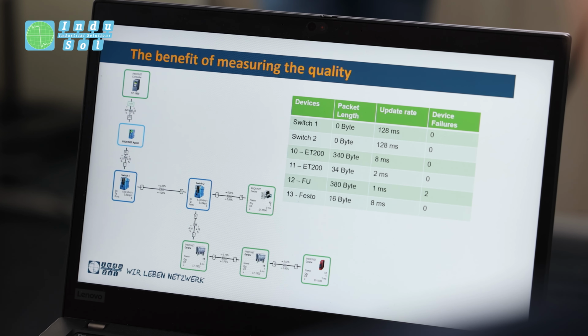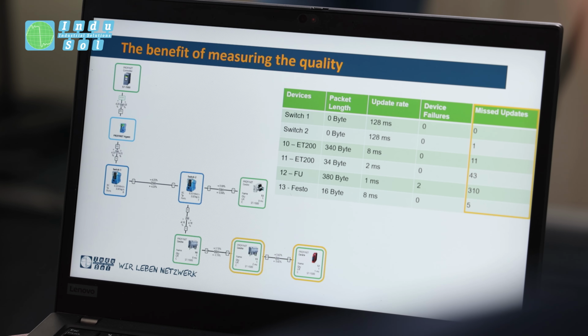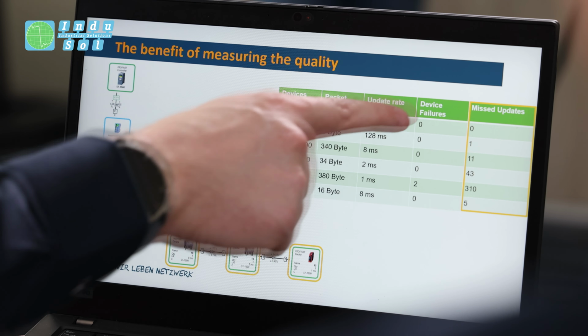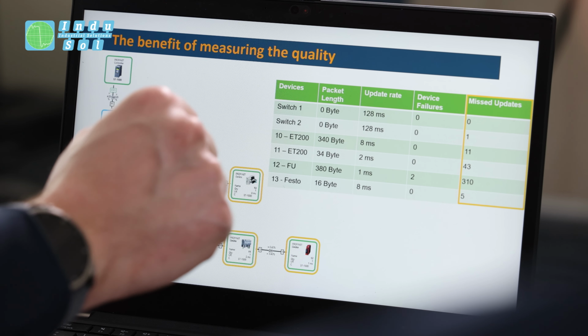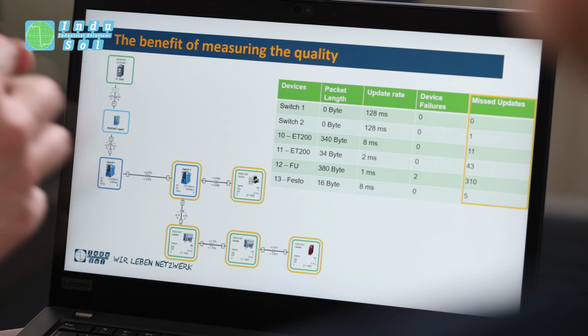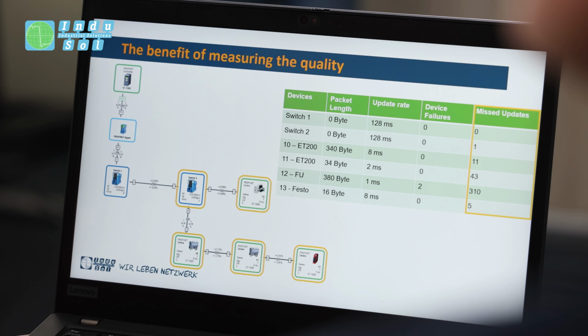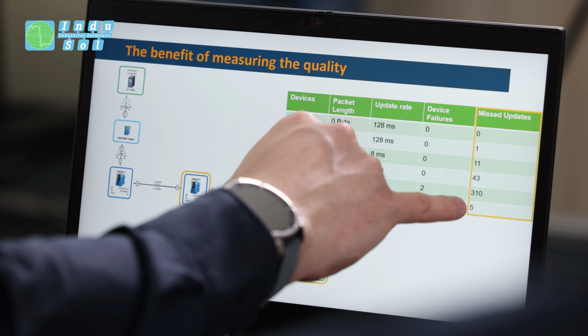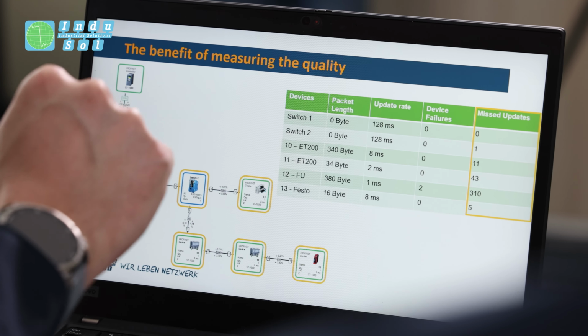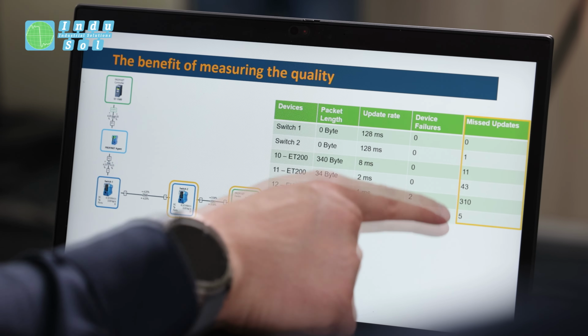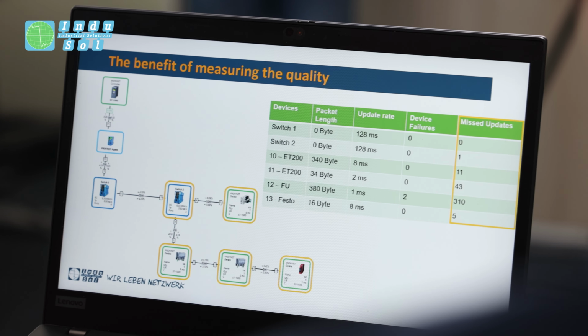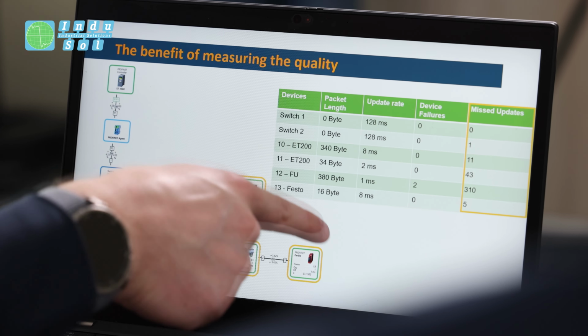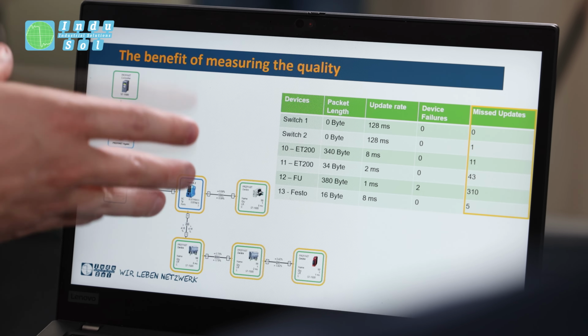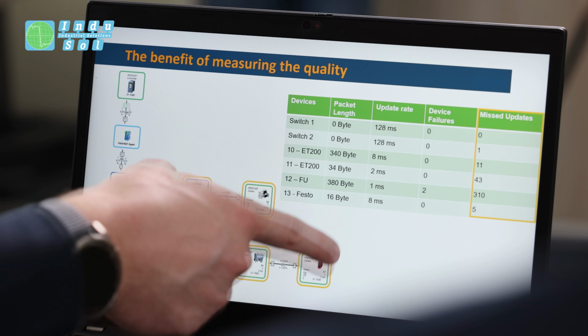What we can do now is give them additional information about missed updates. Often PLCs accept missed updates until a certain point. But if we measure those missed updates, we see it's also this device which had the most, so it is affected the most. But clearly all the other devices here are also affected. With the first look, you don't have to investigate here for the issue, because the root cause is situated here, in this location.